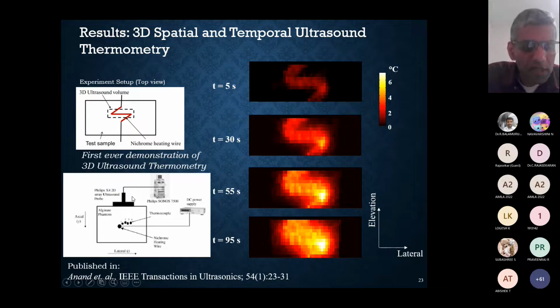This transducer is essentially a 2D transducer, so we can acquire data in 3 dimensions. On the right is a field of view oriented similarly to the nichrome wire, so you can see its zigzag shape. These panels show the temperature rise over time from top to bottom — the first three panels are during heating, the last during cooling. As you can see, we're able to track the temperature rise, mapping both the actual rise and its spatial profile, matching the zigzag shape of the heating element nicely.